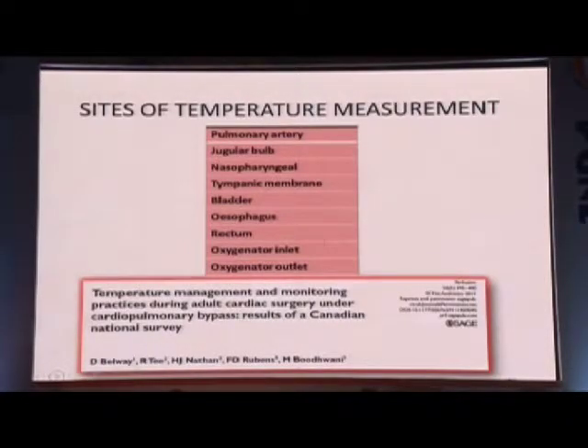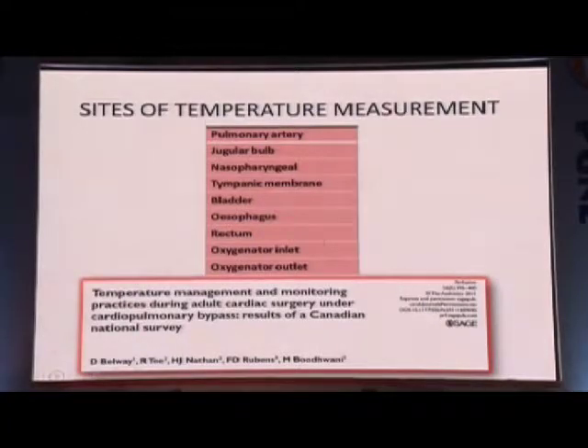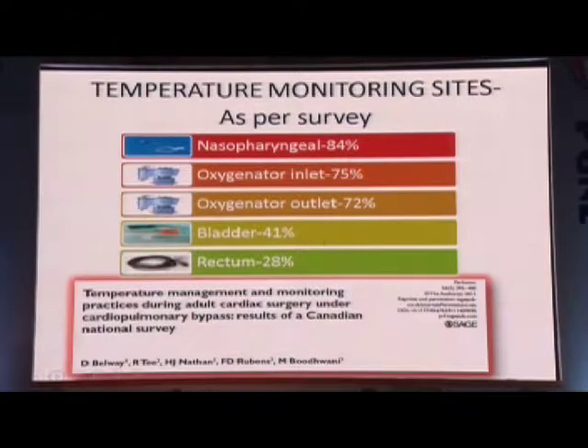Regarding temperature measurement sites — this was a Canadian study. People measure pulmonary artery temperature if a PA catheter is in place. Jugular bulb temperature is more reflective of cerebral temperature. Tympanic and nasopharyngeal are core temperatures. Bladder temperature catheters with temperature monitoring are also used, as well as oxygenator inlet and outlet temperatures. The Canadian study found 84% of centers measured nasopharyngeal temperature, 75% also measured oxygenator inlet and outlet, 41% bladder temperature, and 28% rectal temperature.